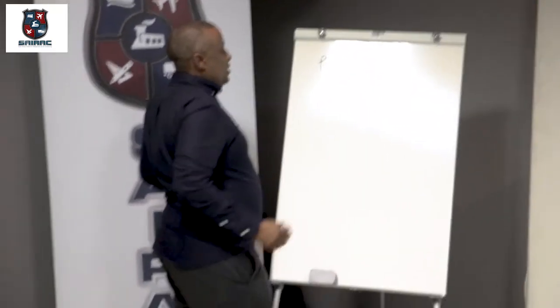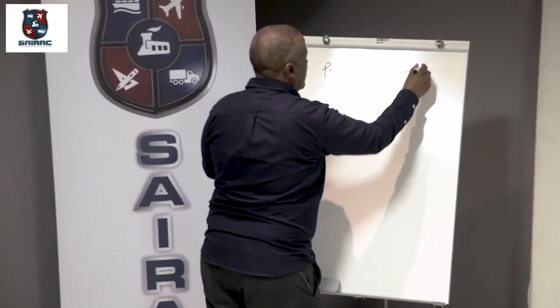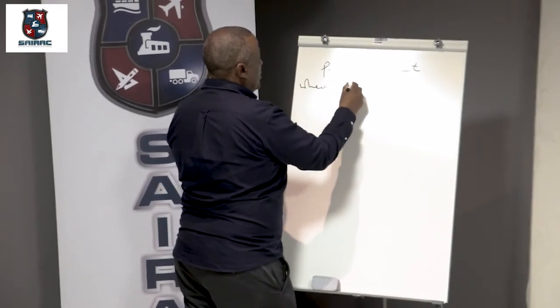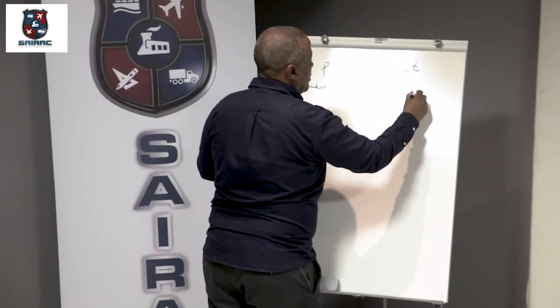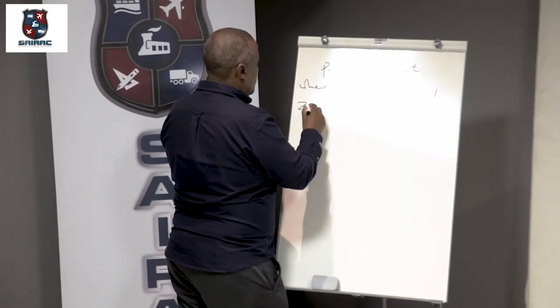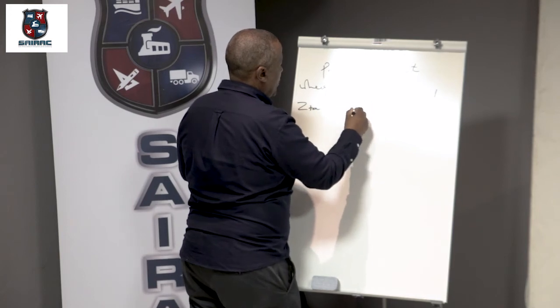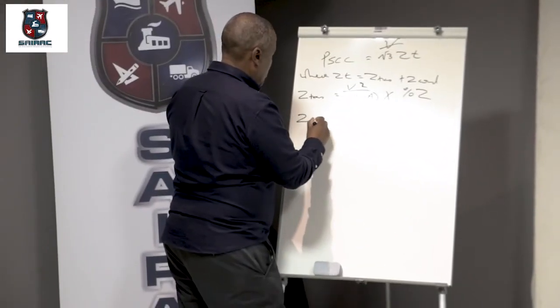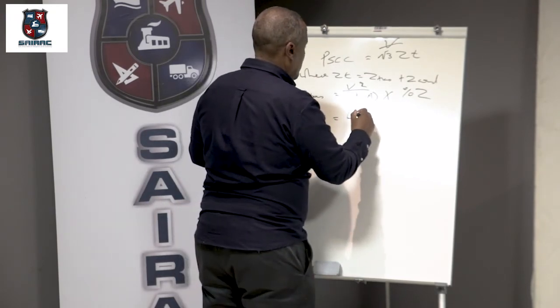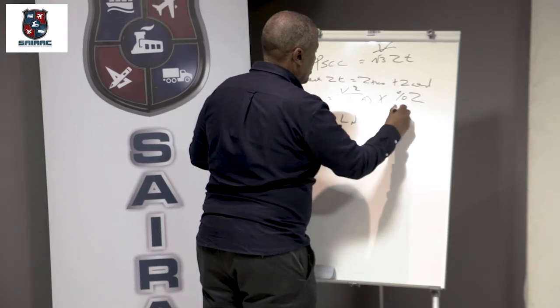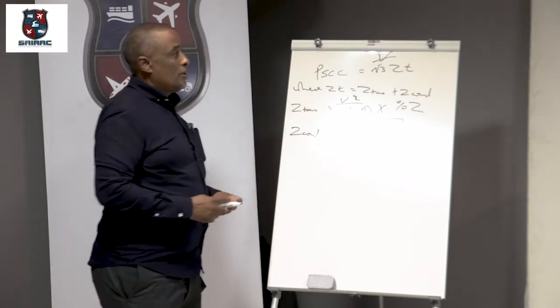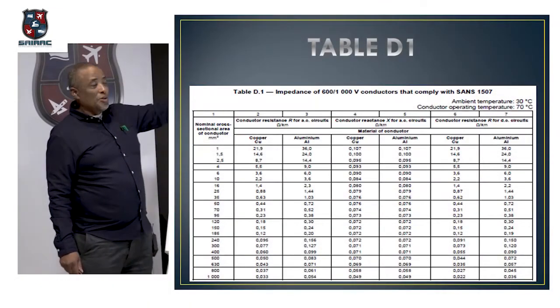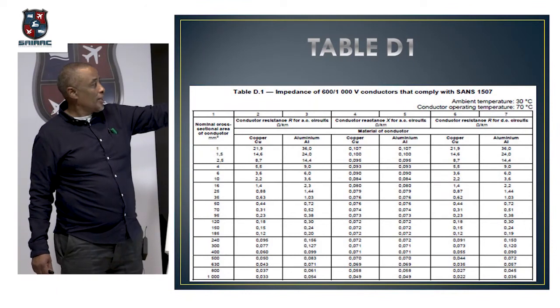Okay, the calculation is quite simple. PSCC is equal to V over root 3 ZT, where ZT is equal to Z of the transformer plus Z of the conductors. Z of the transformer is equal to V squared all over P kVA, times percentage impedance. Z of the conductors is equal to length times the square root of R squared plus X squared, all over 1000. Okay, if we look at table D1, which you'll get in the SANS book, if you want to calculate PSCC.